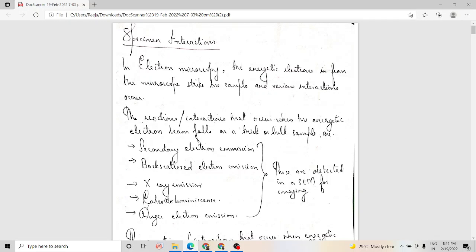First, we discuss the interactions that occur when an energetic electron beam falls on a thick or bulk sample. When an electron beam falls on a thick sample, secondary electron emission, backscattered electron emission, cathodoluminescence, and Auger electron emissions can take place. Out of these, secondary electron emission and backscattered electron emission are the ones predominantly detected by the scanning electron microscope for imaging.